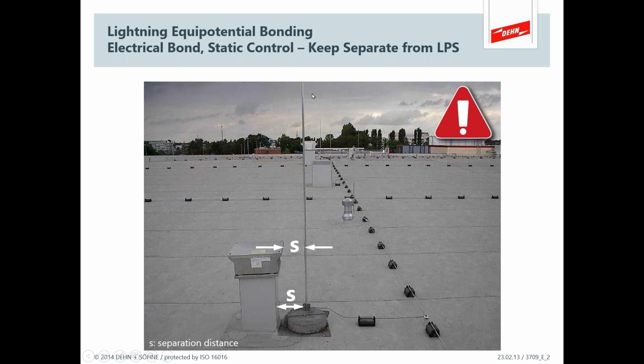Lots of discussion, but here's the point. You have a lightning rod, you have an air terminal, you have a down conductor system, but it's going past an electrical box, and it's too close. You haven't kept it far enough away, because that electrical box has some purpose. It's up there for a reason. It's not just that somebody put that box there because it was the best place to store their radio. They put it there because they have to have this controller box on the roof. It's got a ground wire in it doing its electrical safety thing, but now you've got a high risk of flashing into it. So with lightning equipotential bonding, maybe you should have moved that farther away.